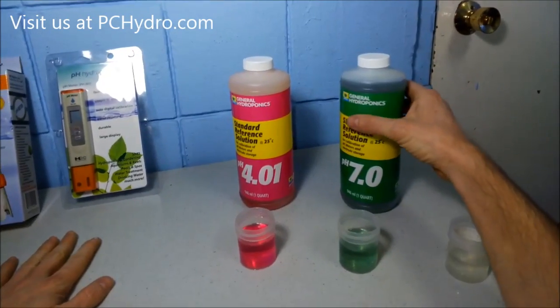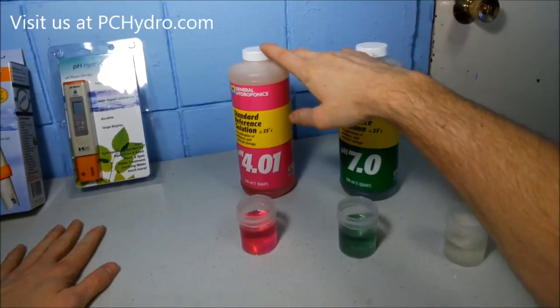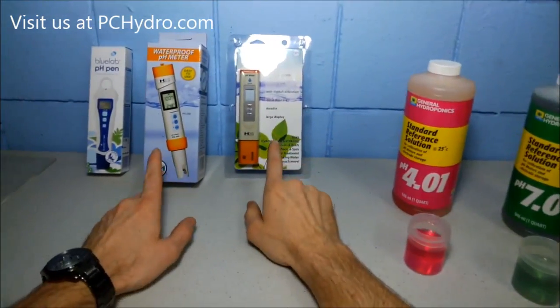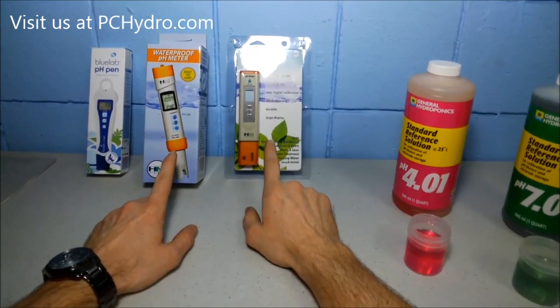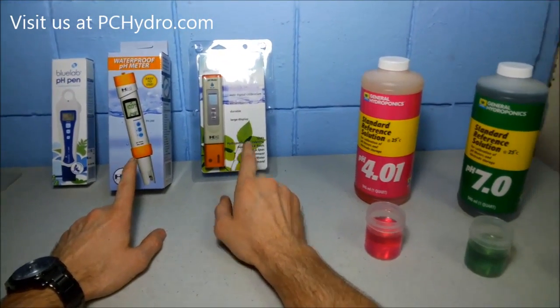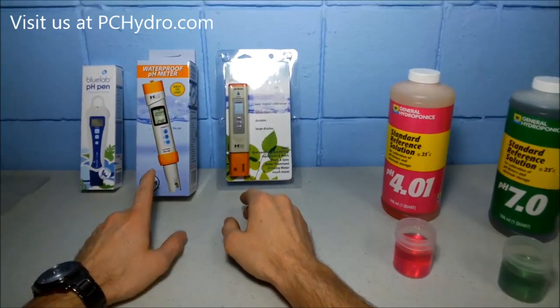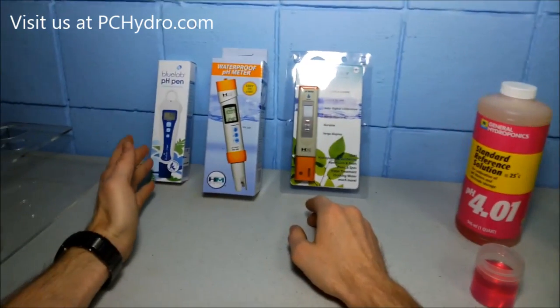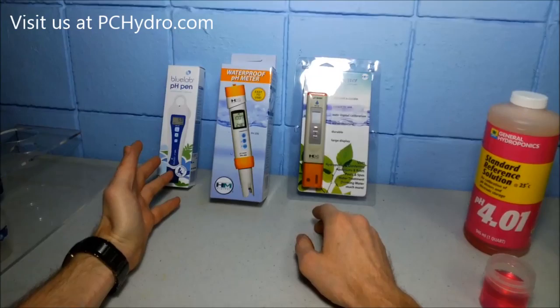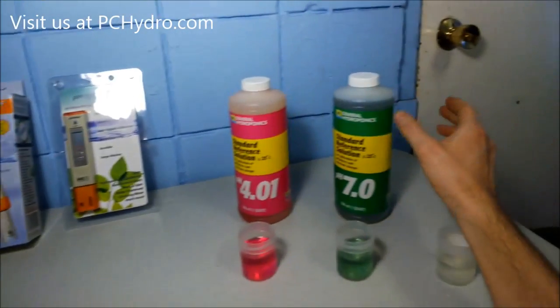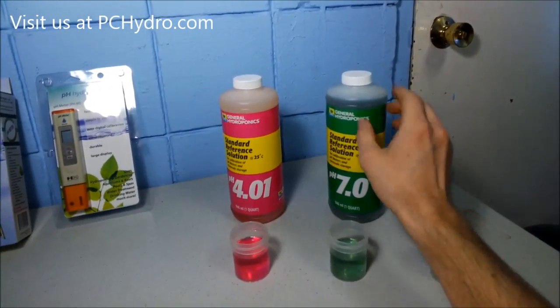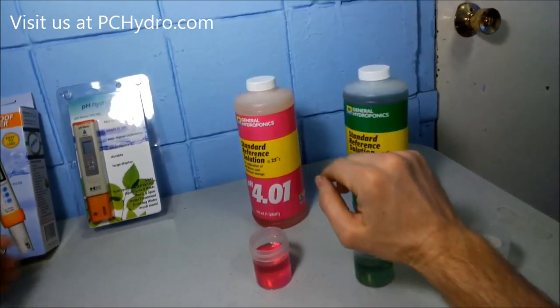We have a 7.0 and a 4.0 solution, and these two pens here use what's called the 2-point calibration. So they calibrate to 4 and they calibrate to 7. The Bluelab, however, uses what's called the 1-point calibration. It only uses the 7.0 calibration solution and doesn't actually calibrate to the 4 at all.